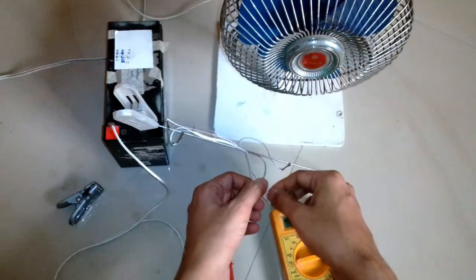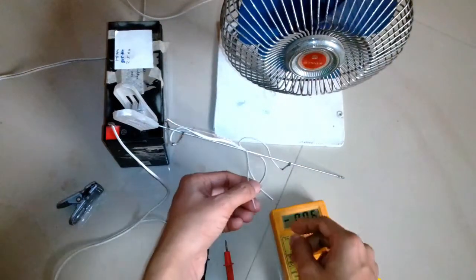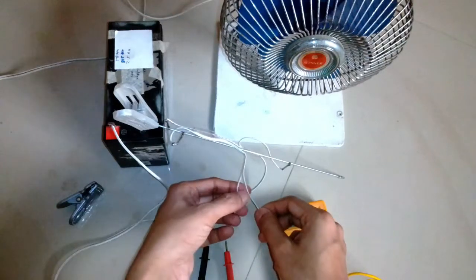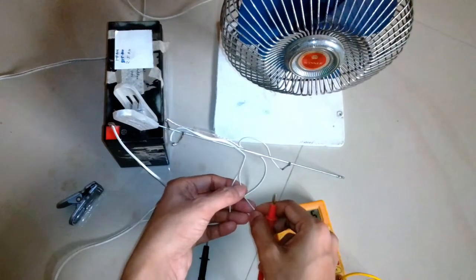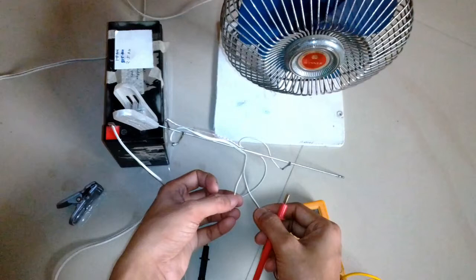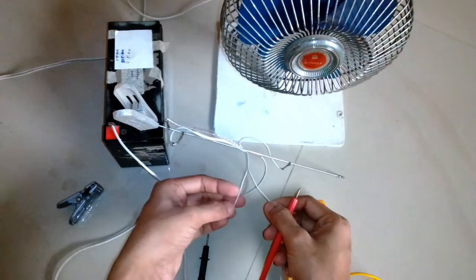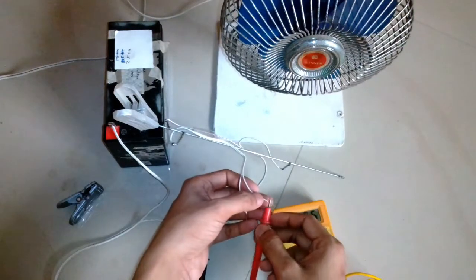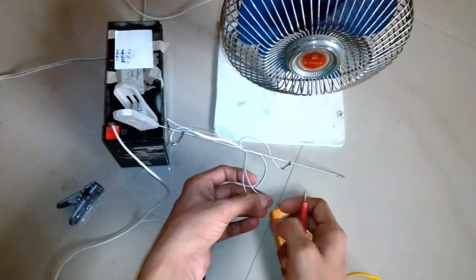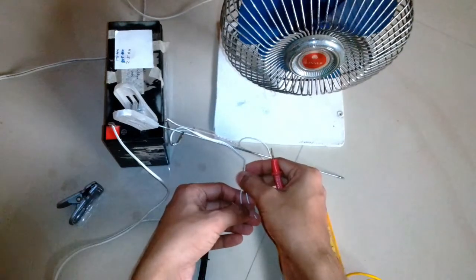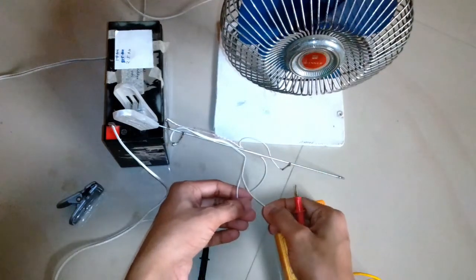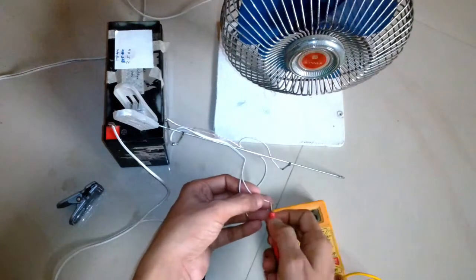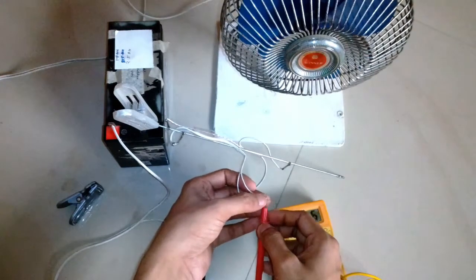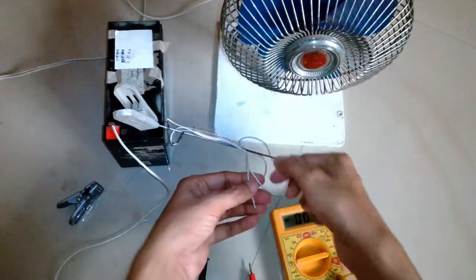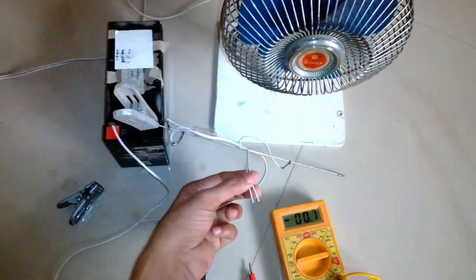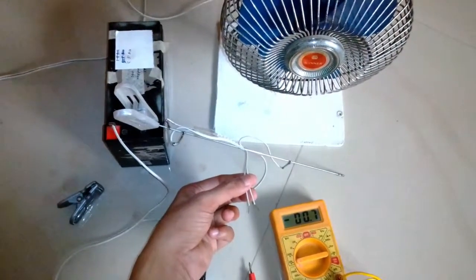Now I'm going to connect it to the 1 millivolt drop point at 1 amp. So that is the shortest distance in the shunt, and with 1 amp load the voltage drop is only 1 millivolt, so I don't have to divide it with any digit. I can straightaway take the reading from the multimeter.